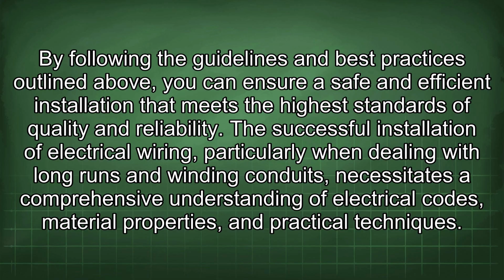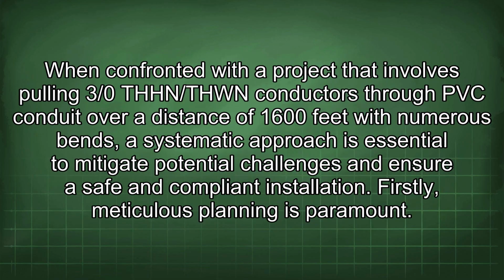The successful installation of electrical wiring, particularly when dealing with long runs and winding conduits, necessitates a comprehensive understanding of electrical codes, material properties, and practical techniques. When confronted with a project that involves pulling 3/0 THHN/THWN conductors through PVC conduit over a distance of 1,600 feet with numerous bends, a systematic approach is essential to mitigate potential challenges and ensure a safe and compliant installation.